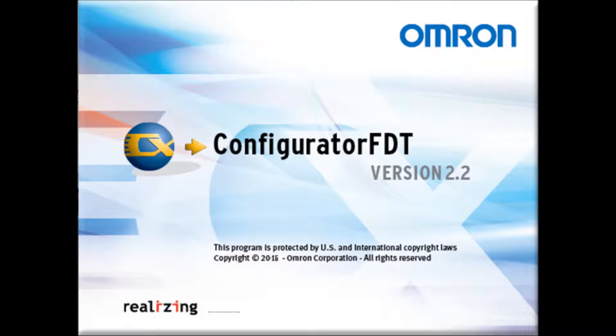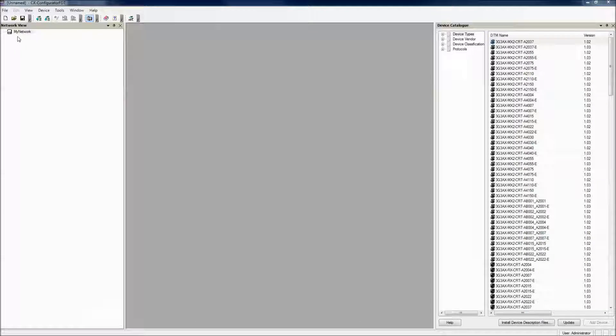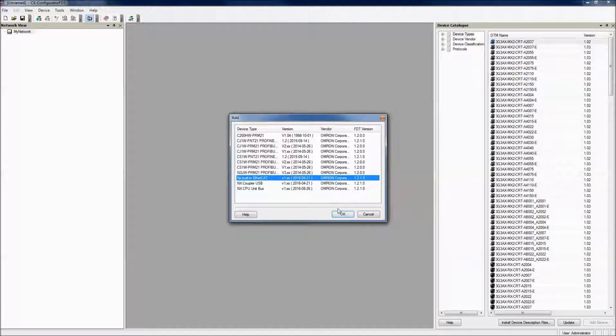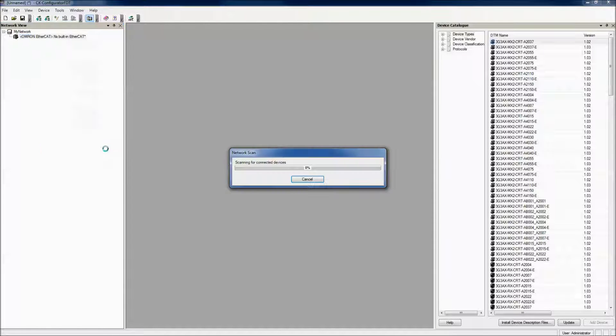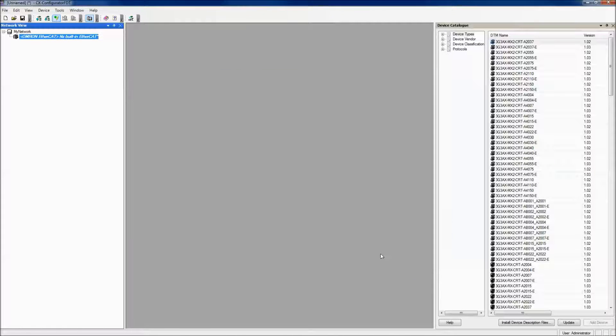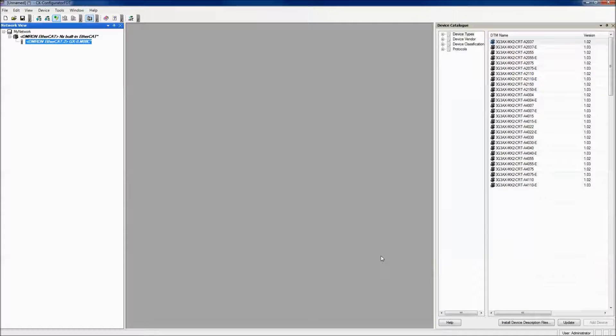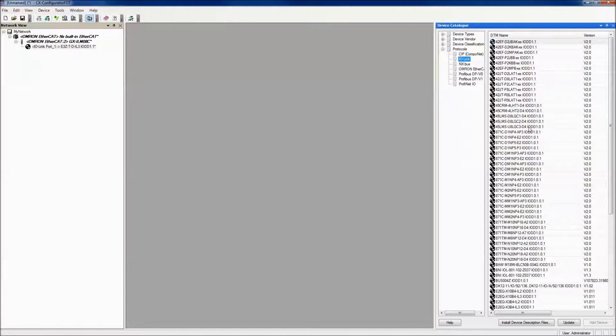Now that my IO-Link master settings are configured, I can change the IO-Link device settings. I've opened CX-Configurator FDT, which is included with Sysmac Studio update 1.16. First thing I need to do is add my NX built-in EtherCAT port. From here, all I have to do is scan my network to add the IO-Link master and the IO-Link devices that are attached. If you don't have the actual network set up, you can go into the protocols and drag in your IO-Link device into the network.